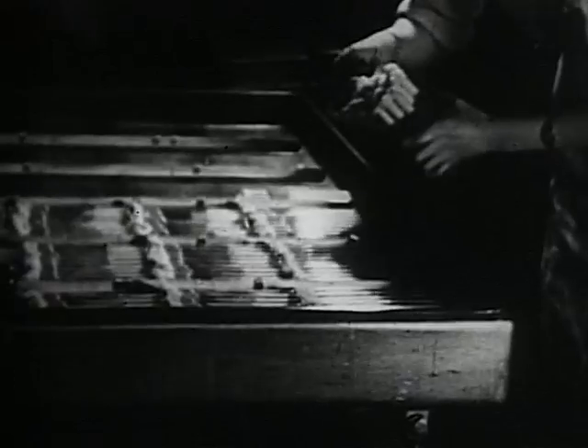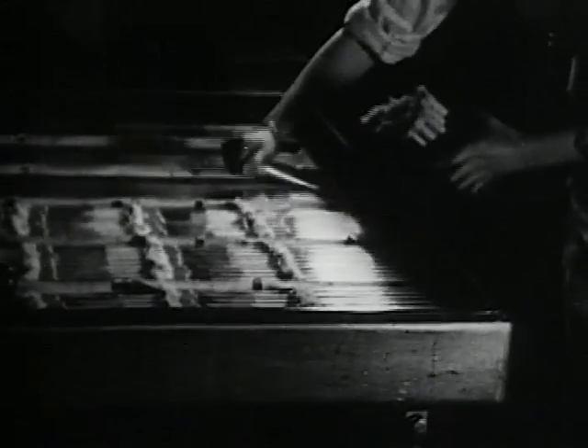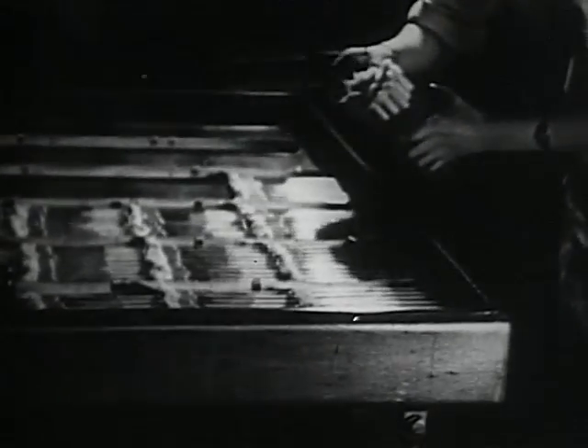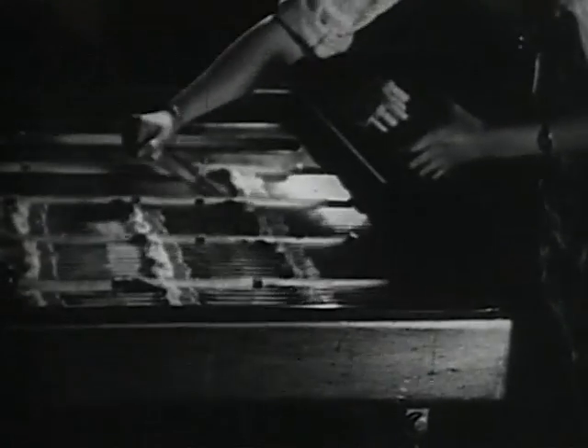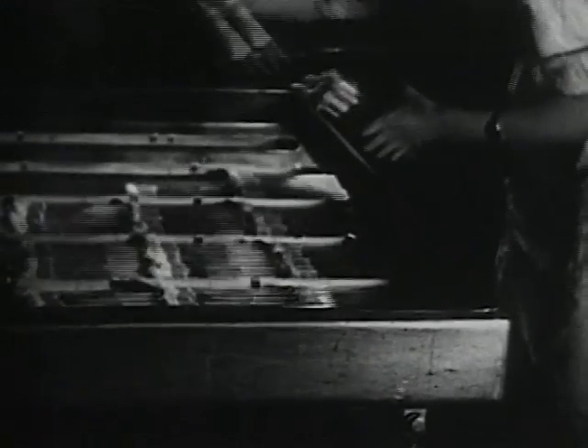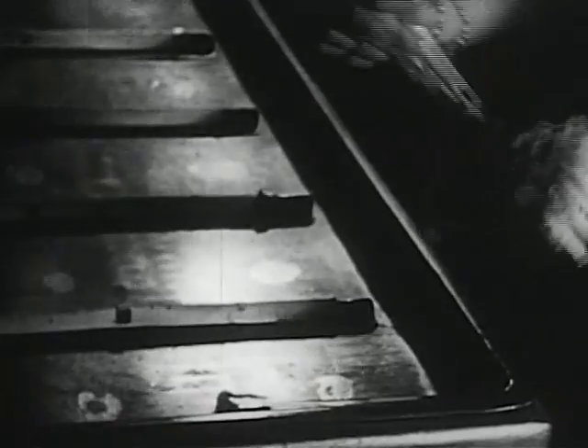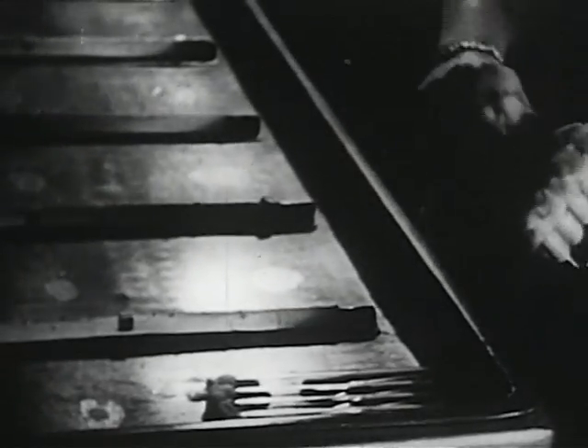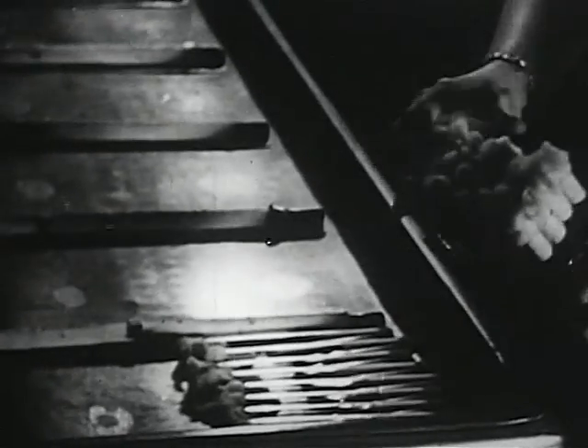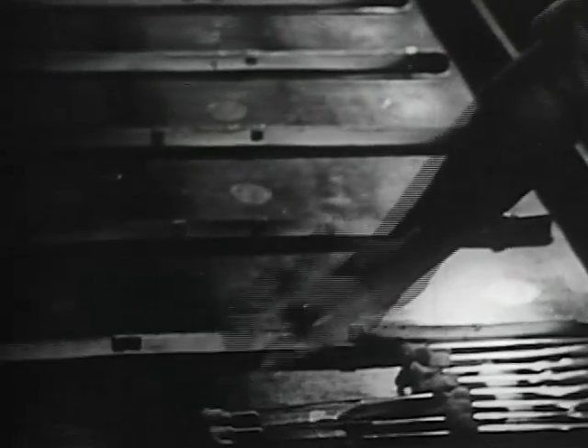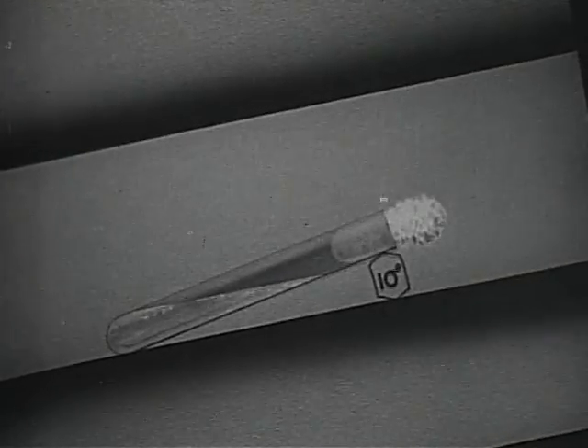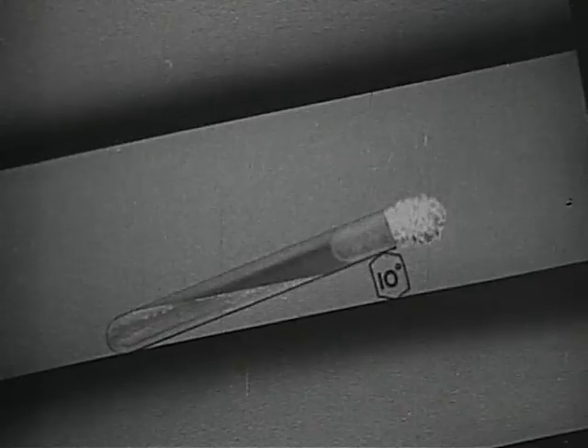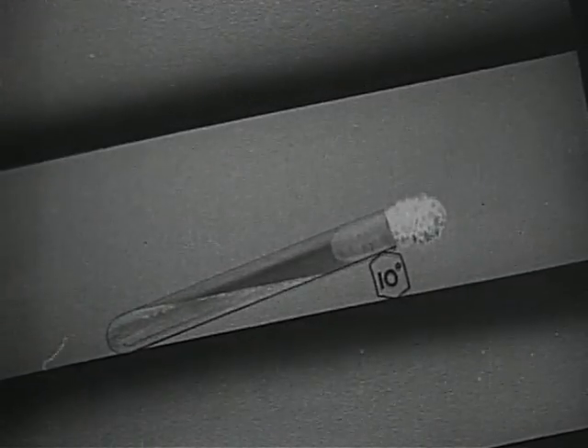The tubes of fluid medium are all placed in this inspissator for the necessary formation of the slant by coagulation. The floor of this inspissator is so inclined that a long uniform slant is formed by the medium within each tube. It is inspissated in this form. Approximately 10 to 12 degrees will provide a suitable slant for seeding the culture.